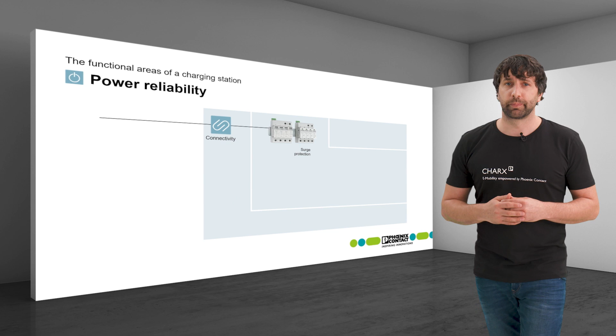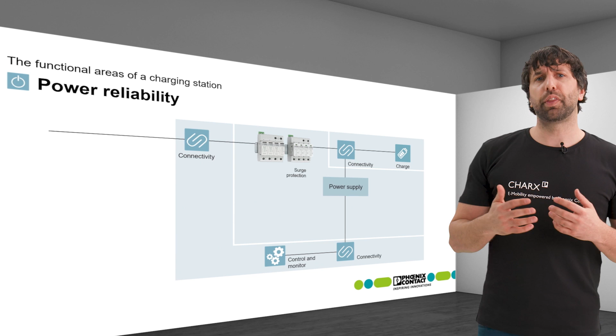Downstream of the surge protection, the supply branches off. One side supplies the functional area charge. Another path supplies the charging controller and other internal components with 12 or 24 volt DC via the power supply unit.